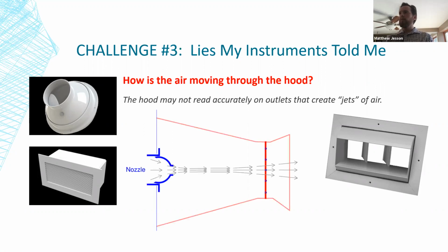If you think about how the air is moving through that hood, in the case of what I call an eyeball, I'm sure there's a better word for it, but everybody knows what I'm talking about when I say eyeball, I think. It's directing that air in a narrow jet, and usually you see them in airports and big open offices to throw that air as far as it can. Well, when you do that, it just hits one tight area of the velocity grid in the hood. So that's going to give you a weird reading. And back to the square root of the sum rather than the sum of the square roots, that's really where that comes into giving you a bad reading.